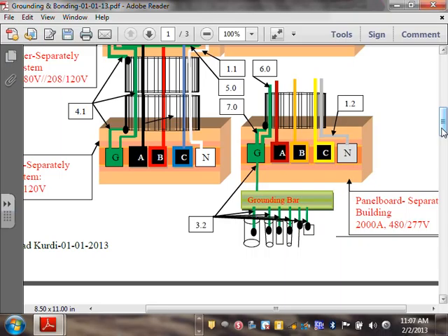Does it make sense? Yes, sir. Yeah, the second building, you always have to bring the ground over. You cannot feed your building from a separately derived system if you didn't bring your grounds over and you tried to ground the neutral and bond it to neutral. You have to bring your equipment grounding conductor to the second building, and you have to bond your equipment grounding conductor to the grounding electrode system. Right here, here's my equipment grounding conductor coming to the ground bar and tied to the grounding electrode system via a grounding electrode conductor. What you don't do is bond the neutral and the grounding bar together.